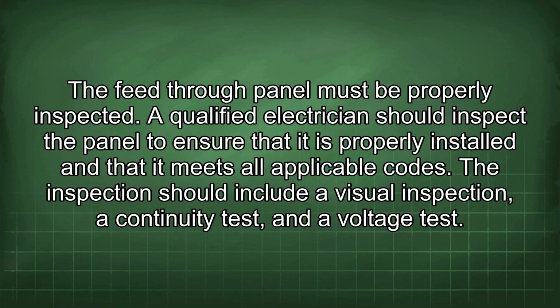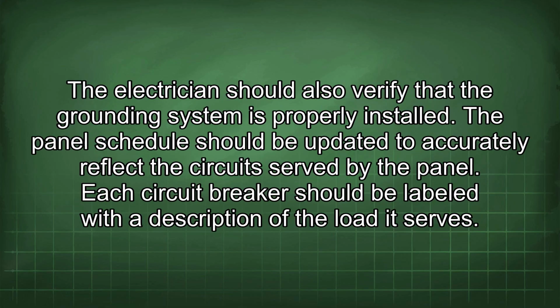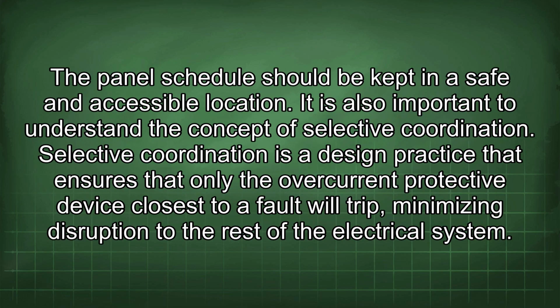The feed-through panel must be properly inspected. A qualified electrician should inspect the panel to ensure that it is properly installed and that it meets all applicable codes. The inspection should include a visual inspection, a continuity test, and a voltage test. The electrician should also verify that the grounding system is properly installed. The panel schedule should be updated to accurately reflect the circuit served by the panel. Each circuit breaker should be labeled with a description of the load it serves. The panel schedule should be kept in a safe and accessible location.